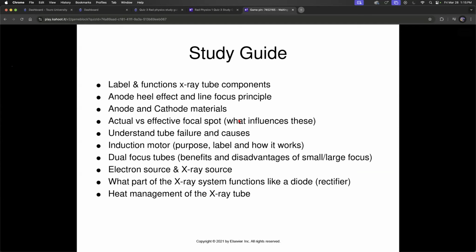Let me get Raul and then Jacqueline. What do you got? I was going to say, just warm up the tube. Fantastic. Jacqueline, what are we ill-advised to do? Send high heat to a cold anode. Fantastic.